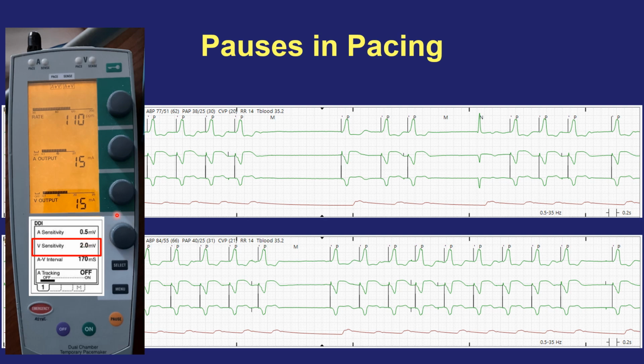So if you see these pauses occurring, you can make this number higher and higher until you stop seeing these pauses, and then it will continue to sense the QRS complexes, which usually are a larger amplitude signal than the electrical noise that may be causing inhibition of pacing. You can also, in simpler types of pacer boxes, see a dial that will have ventricular sensitivity, and you'll see numbers, and you can turn that dial to higher and higher numbers, which makes the sensitivity lower and lower to prevent inappropriate inhibition of pacing.